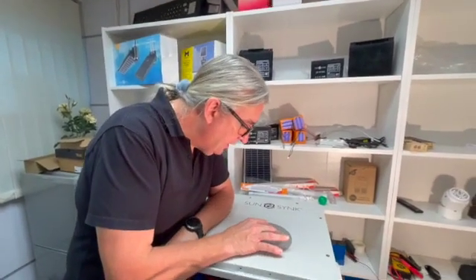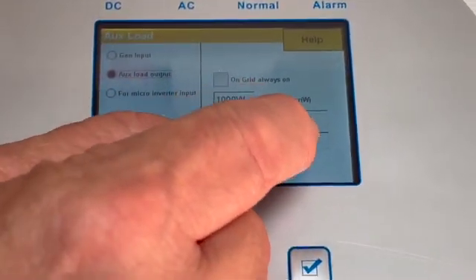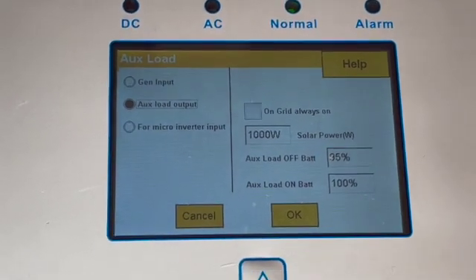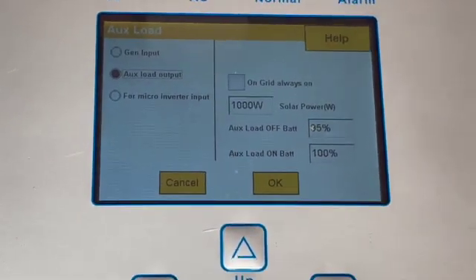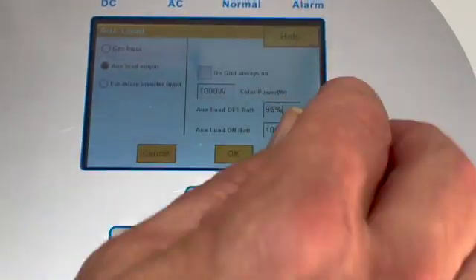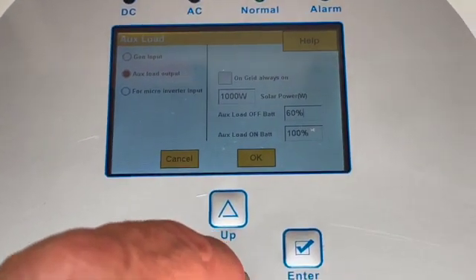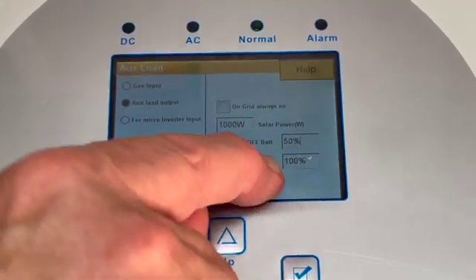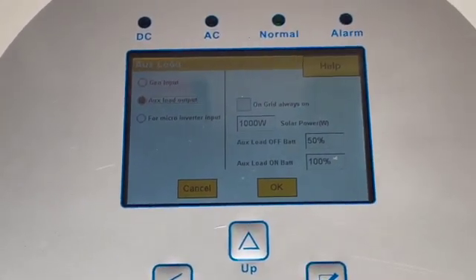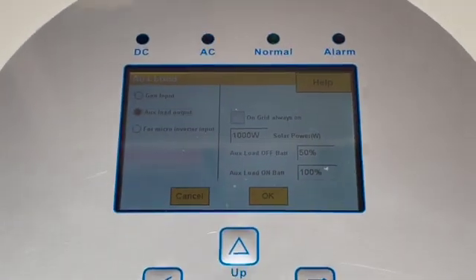Let's go back to auxiliary load. There are several settings here: the point at which the auxiliary will go off and the point at which it will come on. Currently it's set so the auxiliary load comes on at 100 percent and goes off at 95 percent. These figures are totally changeable to whatever suits you. For instance, you might want the auxiliary to switch off at 50 percent if you're using it for non-essential loads.